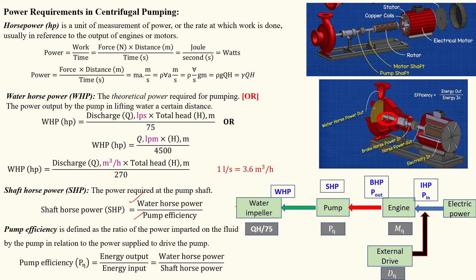Pump efficiency is energy output divided by energy input. The energy output from the impeller is the water horsepower. The pump transfers energy into the water through the impeller — that is the output. The input to the pump is the shaft horsepower. So pump efficiency equals water horsepower divided by shaft horsepower, and therefore shaft horsepower equals water horsepower divided by pump efficiency.